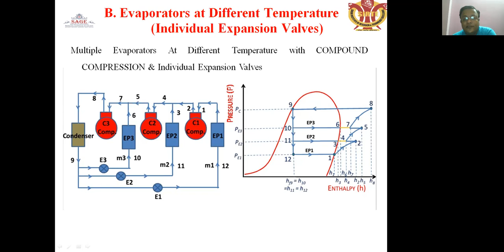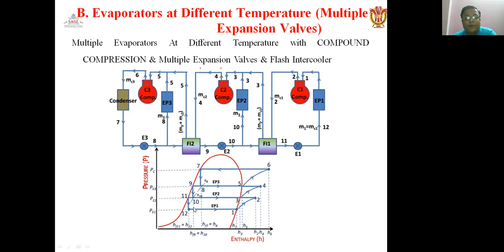There are 3 compressors and multiple evaporators at different temperatures, with compound compression and multiple expansion valves, and a flash intercooler is also used. The flash intercooler is in between C1 and C2, and C2 and C3. This is an improved system arrangement in which the refrigeration effect will increase more and more, and the compression will require a little more work. Overall COP of the system will be improved.